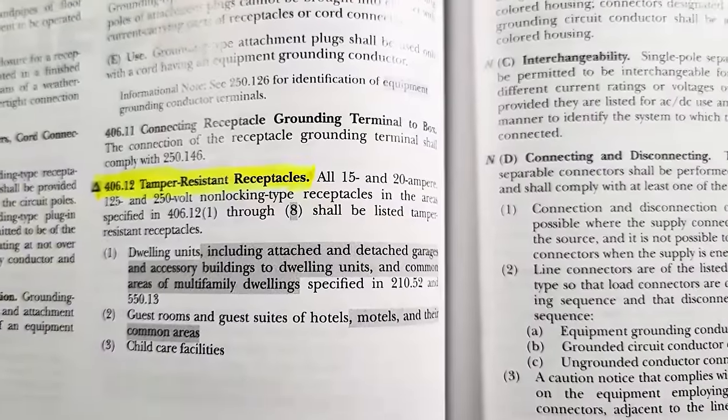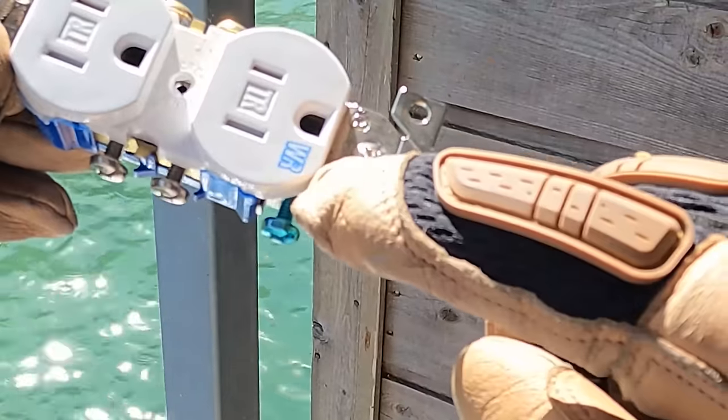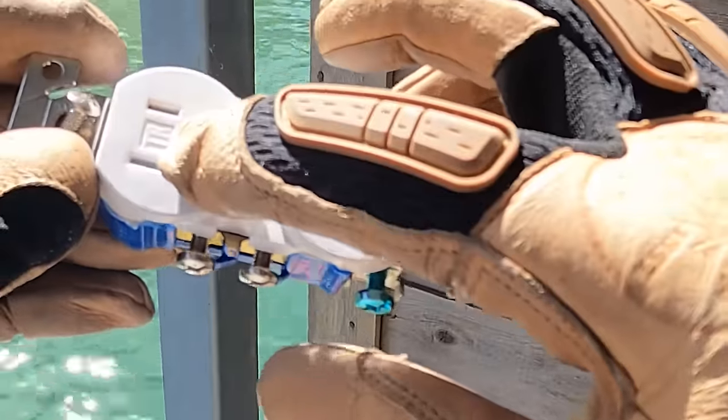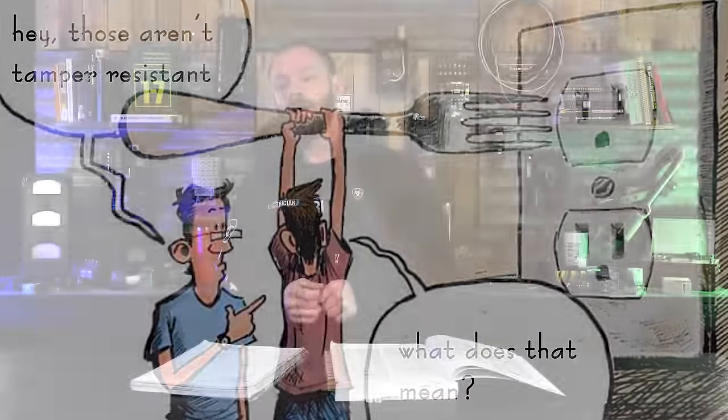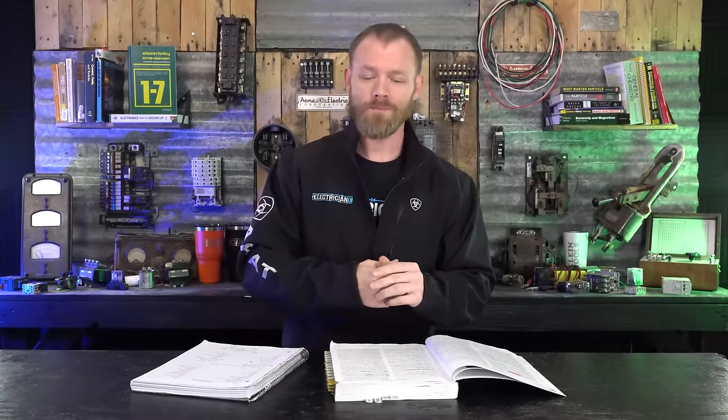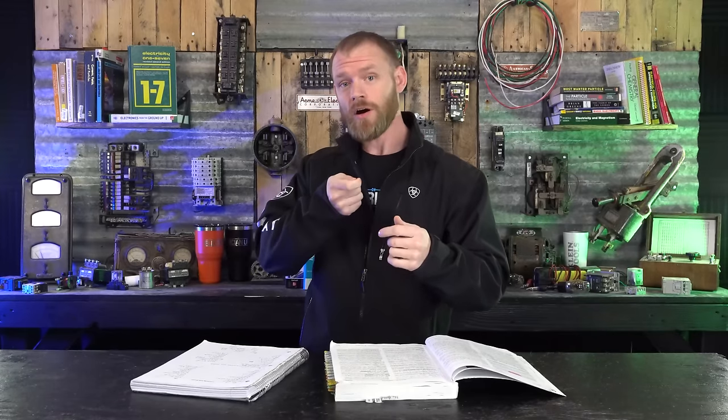Next thing we have is a tamper resistant receptacle or a TR receptacle. Sometimes you'll see weather resistant, tamper resistant. So they'll say WRTR if you use those outdoors. So they're still tamper resistant, meaning that somebody can't go stick a piece of metal inside and shock themselves like children used to do. Tamper resistant receptacles are required to be put pretty much everywhere that somebody could potentially go and try to stick something into a receptacle. They've got these little plastic flaps on the inside of them. And the only way to get the plastic flaps to fold in when you plug something in is to put equal pressure on both sides.